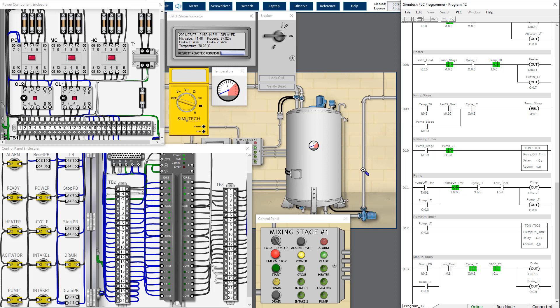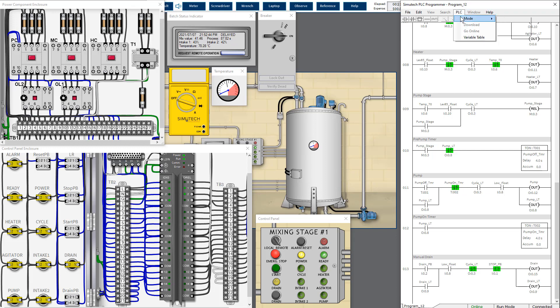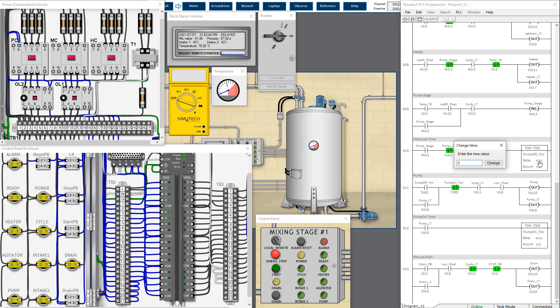We want five bursts. Previously we got six bursts, so we need to modify the timers. We can change the pump-on timer from four seconds to five seconds so the pump runs longer each burst, reducing the number of bursts. At the same time we need to reduce the process time by reducing the waiting timer from four seconds to three seconds — less waiting time means the mixture pumps out faster and the overall process time will be shorter. We set the PLC mode to test, change the wait timer to three seconds and the pump timer to five seconds, then set the PLC mode back to run and start the process.